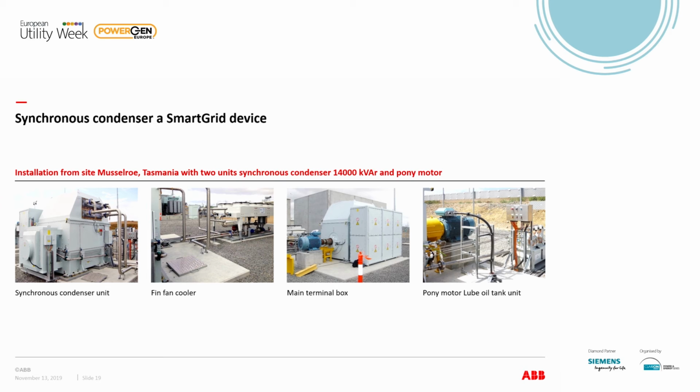In reality, this is also an advantage for them. It makes it easier for transport. The wind farm could use the synchronous condenser also for their internal balance of plant for reactive power, which means that they could take out more active power from their inverters. Otherwise, they have to use the inverter to handle reactive power, and with this degrade a little bit their inverter capacity on the active power, which they get paid for.